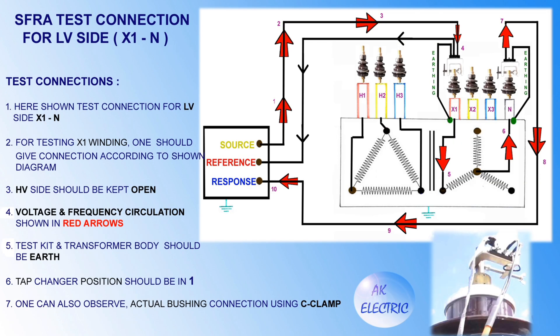For the SFRA test connection on the LV side — X1 to neutral: connections are made as shown in the diagram for testing the X1 winding. The HV side should be kept open. Voltage and frequency circulation is shown in red arrows. The test kit and transformer body should be earthed, tap changer position at one, and bushing connections are made using C clamps as shown.